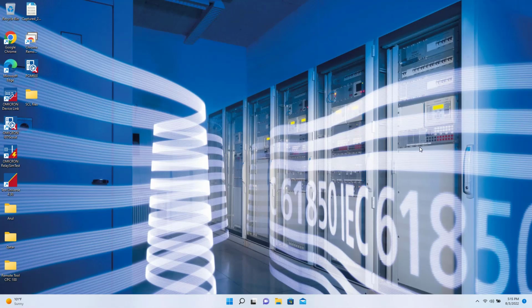There we import the ICD file and merge with the system specification description, and we define the IED name, IP address, and we add the specific data set for the different set of requirements, and we map those data sets to the control blocks, like the report control block, GOOSE control block, sample value control block. Also, these different types of control blocks will be assigned to the client devices, also subscribers within the project.